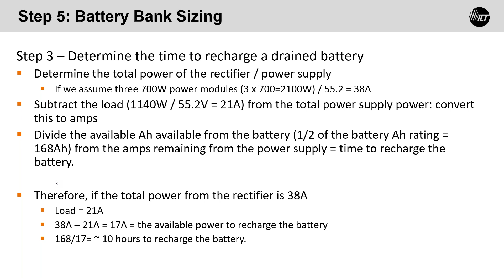So we subtract 21 from 38. 38 amps is from the rectifier. We end up with 17 amps. That's how much power we have available to recharge the battery. So if we take 168 divided by 17, we end up with about 10 hours to recharge the battery. And as I mentioned earlier, these numbers are ballpark numbers, and they're based on worst case scenarios. So often, if everything's healthy, if the battery's healthy, and your loads aren't running 100% all the time, these numbers will be better. But it gets us in the ballpark.